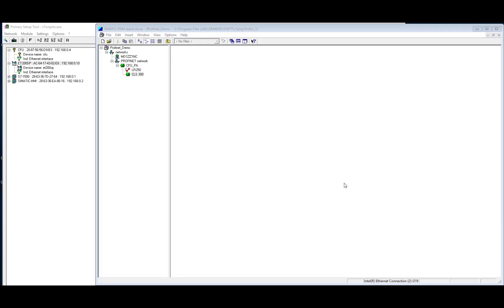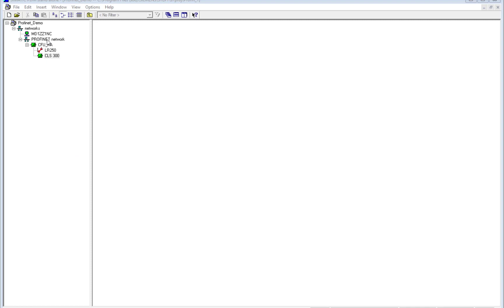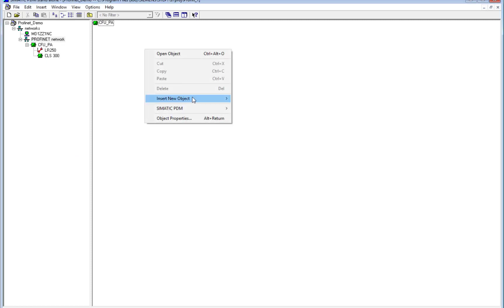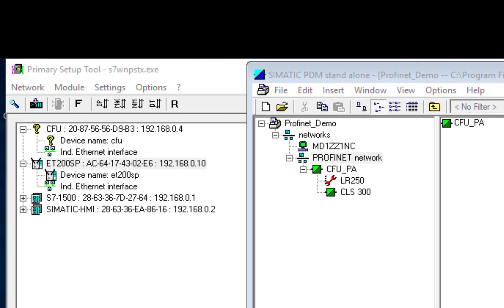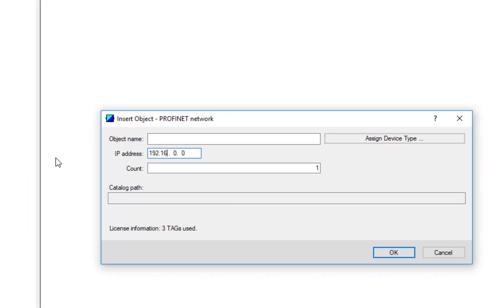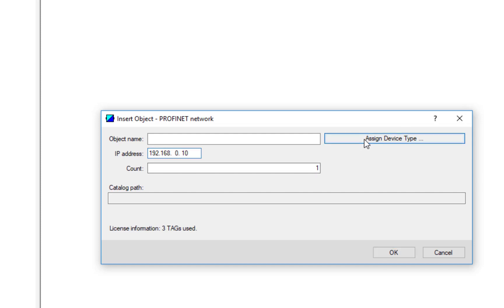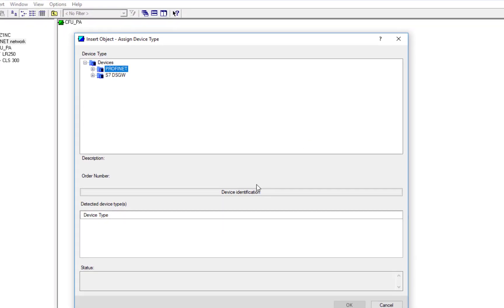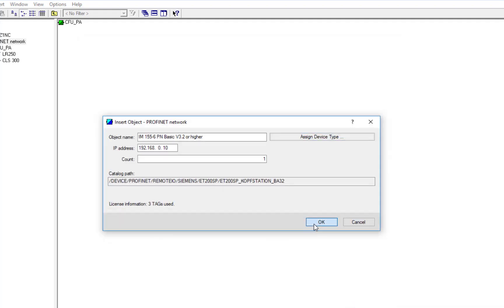So we've now added the Compact Field Unit, so the second part of the IO structure is the ET200SP. This is a little bit trickier because the scanning of the analog card cannot be done by a Live List, so you're going to have to have a little bit of knowledge about the project. So if we click PROFINET network, insert new object, and the IP address here of the ET200SP is 192.168.0.10. And again, we can click on Assign Device Type and get PDM to tell us what is connected. So that's the simple bit.